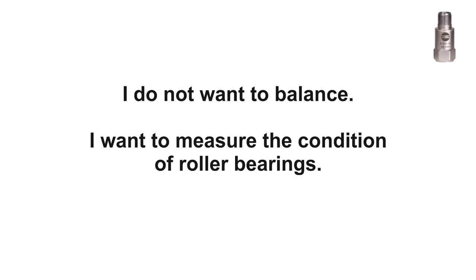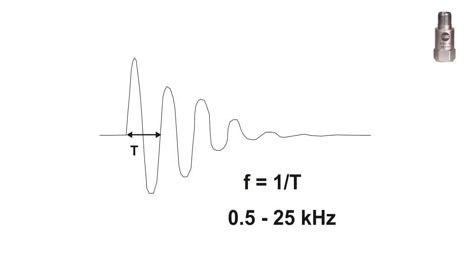For such measurement I do not need the low frequency. When the ball is passing the scratches or through bearing pittings on inner and outer races, then the shocks appear in time signal. The natural frequencies are very high. Typically between 500 Hz and 25 kHz. We do not need to measure low frequencies.